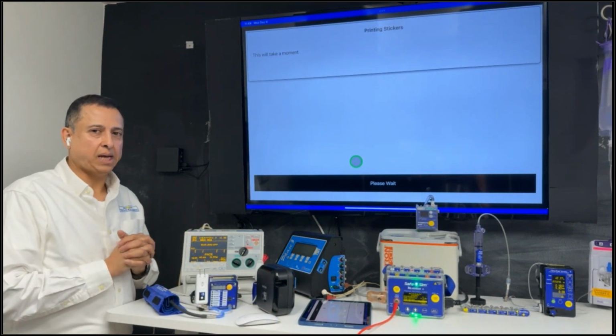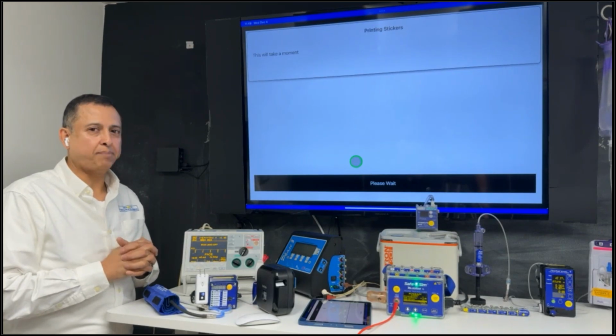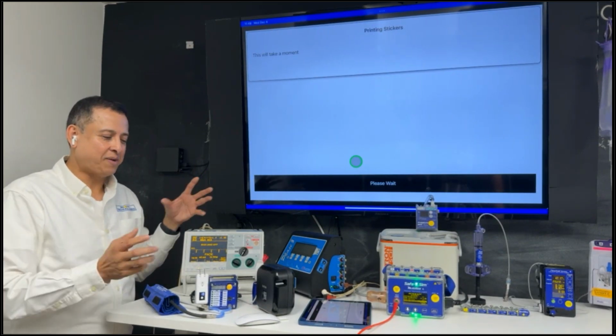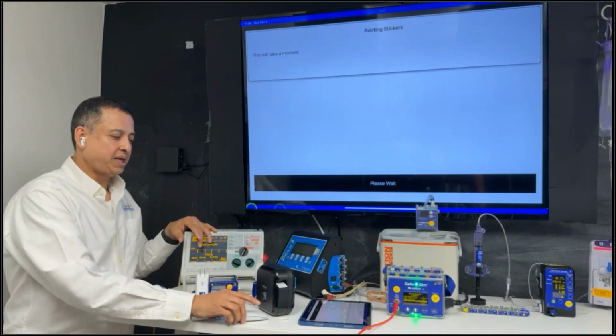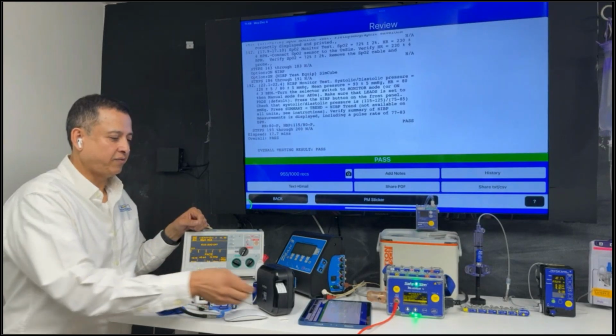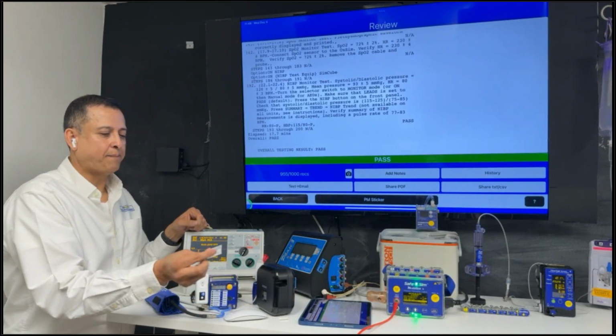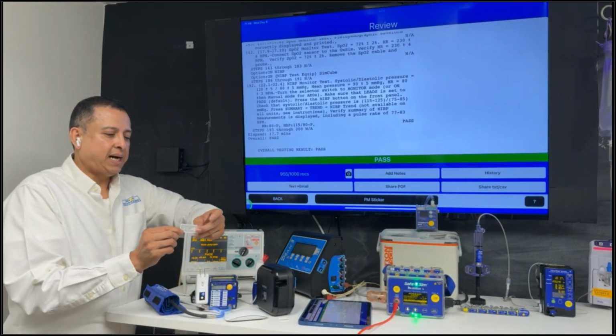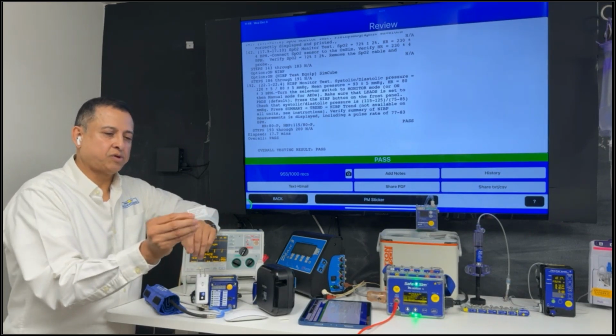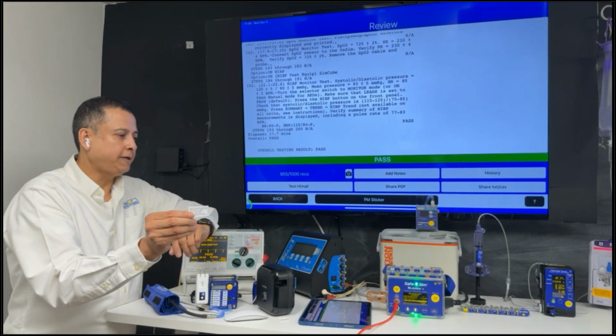We heard from a lot of customers around the country that printing PM stickers is a chore. If you're buying big rolls of PM stickers and trying to manage that, or the technician's having to manually write one out and then put tape over it and attach it to the medical device. So the Brother label maker makes it real simple. It's printed, and then you just peel back the adhesive and attach it to the medical device. So it's pretty small, customizable to however you want.